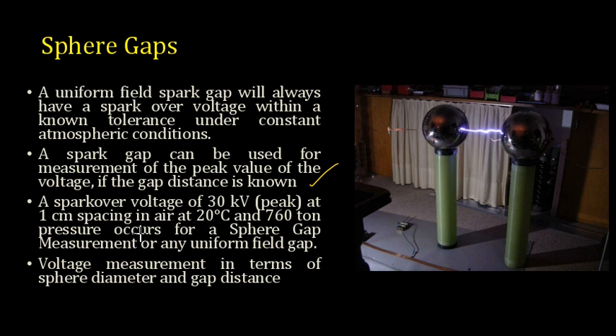In the previous slide, I think I mentioned this is 22 kV. It is not 22 kV. It is 30 kV per centimeter peak value, and at this particular value you will have a flashover. You have to consider standard conditions of 20 degrees Celsius and pressure of 760 torr. This is for a uniform field gap.